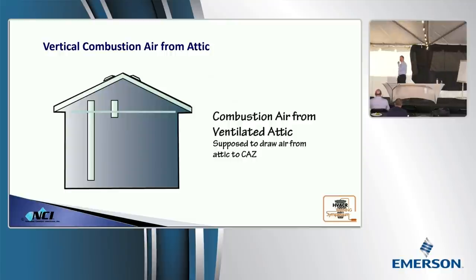Now, there's a situation in some parts of the country, like Arizona, where we stick things on top of the roof that are temperature controlled. What are they? Oh, powered attic ventilators. Gets hot in the attic, kicks the fan on. I could never convince my dad that these were bad things. Some guys are set in their ways. What does that do to the attic? You just put the depressurization on steroids. Now the assumption is, oh, it's going to pull all the air through the eave. The air doesn't know that, just like with combustion air. It has no clue which way it's supposed to go. We have to direct it. It's going to pull right through those combustion air ducts, and it can depressurize that main space.